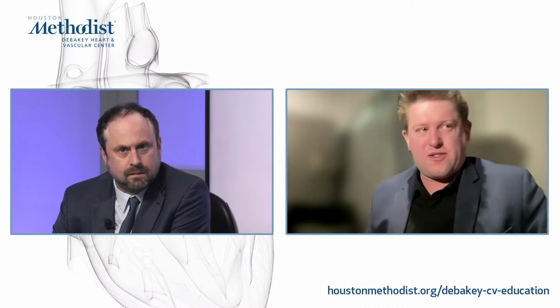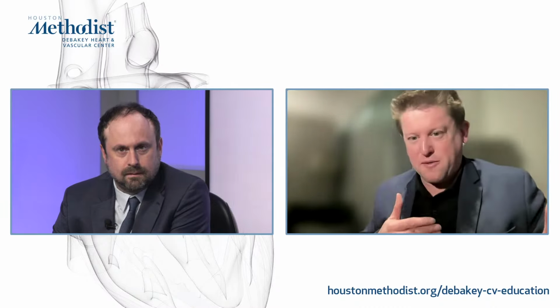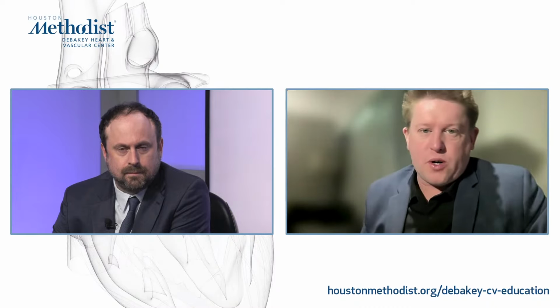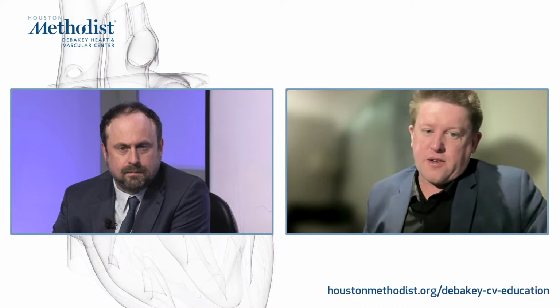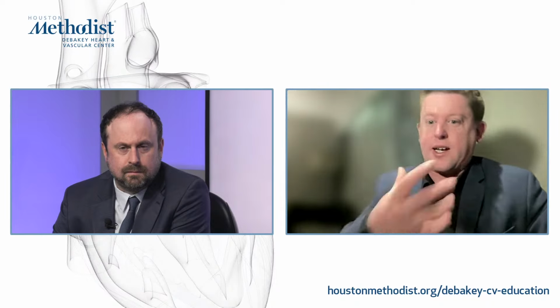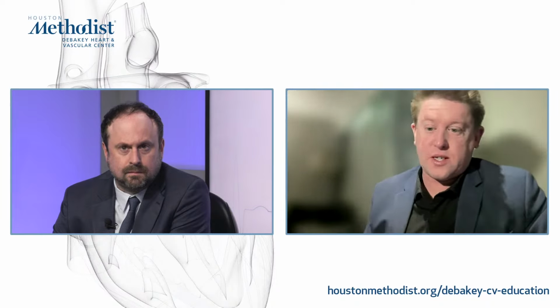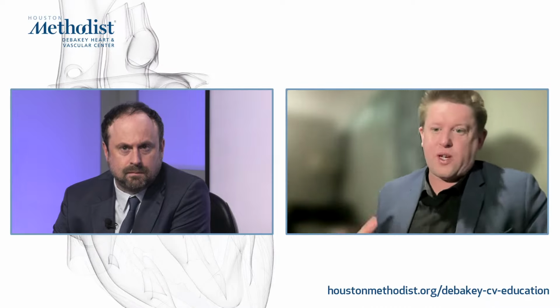And because you remove the operator's speed of analysis as well, we are looking at really speeding up the time it takes to not only collect the measurement but also create the diagnosis, and do that while the person's going about their day, so they don't have to stay still. Basically, one of the biggest challenges with ultrasound is the motion artifacts you get if the patient's moving, or if they're uncomfortable, or if the thing that you're trying to image inside the body is also moving. You get huge motion artifact problems. By stripping it right down to measurement instead of imaging, you should overcome a lot of those challenges.